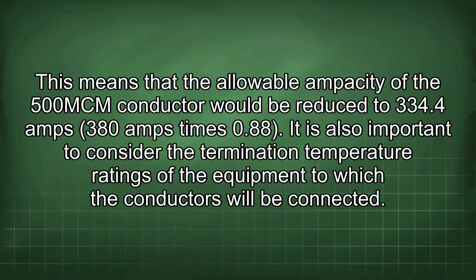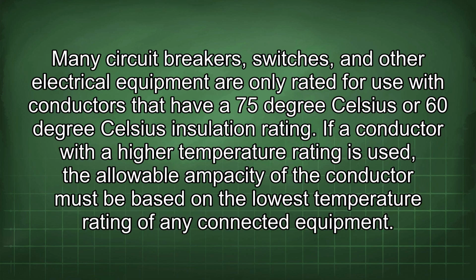0.88. It is also important to consider the termination temperature ratings of the equipment to which the conductors will be connected. Many circuit breakers, switches, and other electrical equipment are only rated for use with conductors that have a 75°C or 60°C insulation rating. If a conductor with a higher temperature rating is used, the allowable ampacity of the conductor must be based on the lowest temperature rating of any connected equipment.